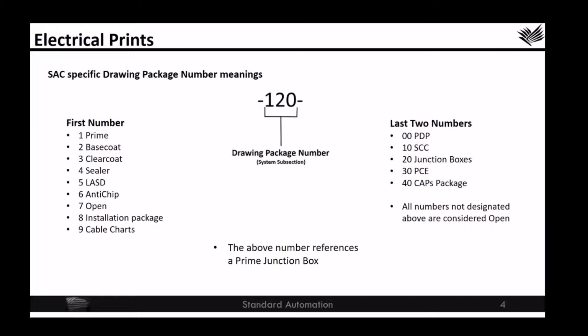So if it relates to the SCC, it'll have the 10 for the last two digits. If it is a type of a junction box, it'll have a 20 as the last two numbers. And then we have things like PCEs or pneumatic control enclosures as well as controller application packages too. For the 120 that we see in this system, that number would reference a prime code for a number 1 in the first digit, and then a junction box for a 20. So a 120 would be a prime junction box.